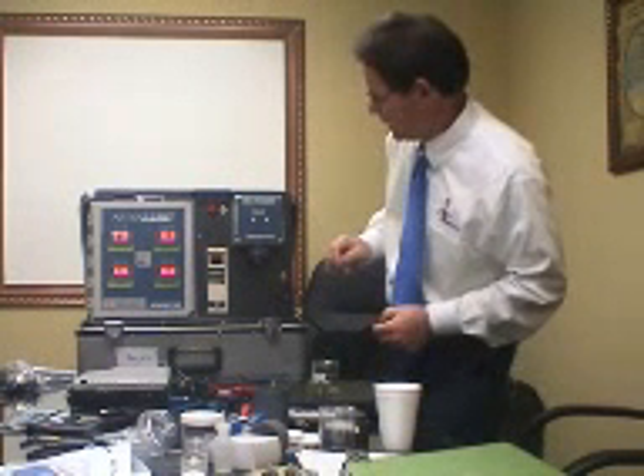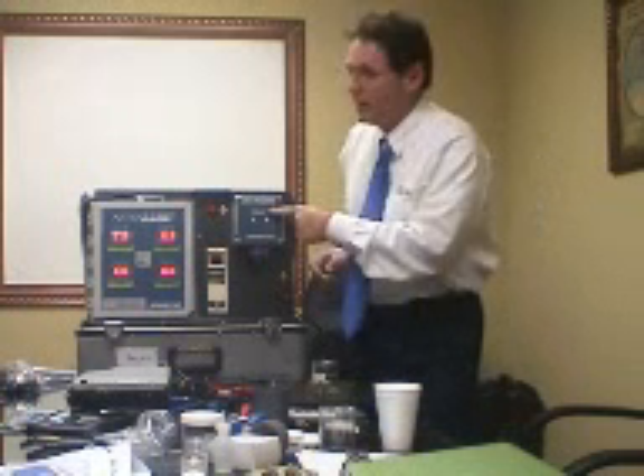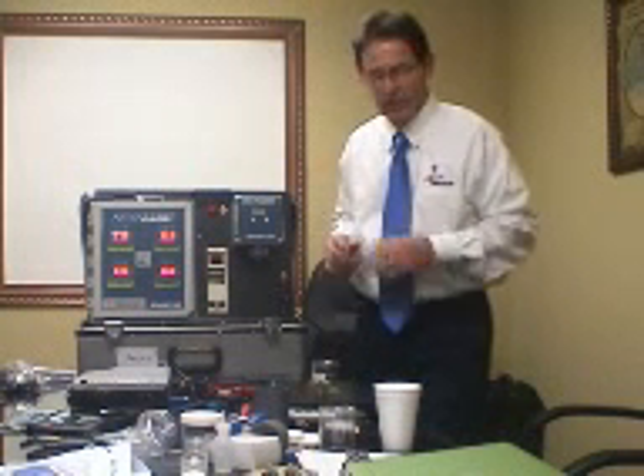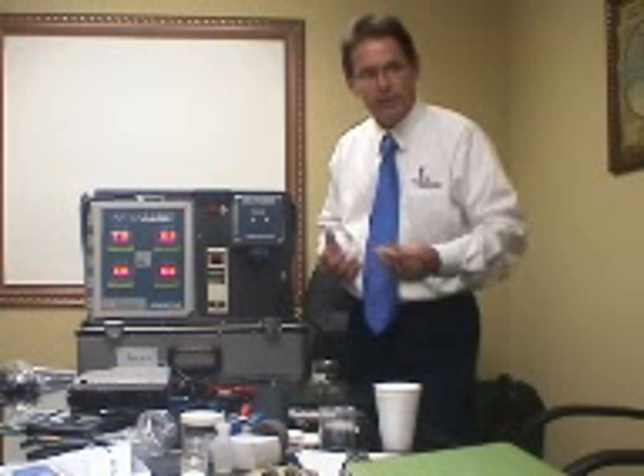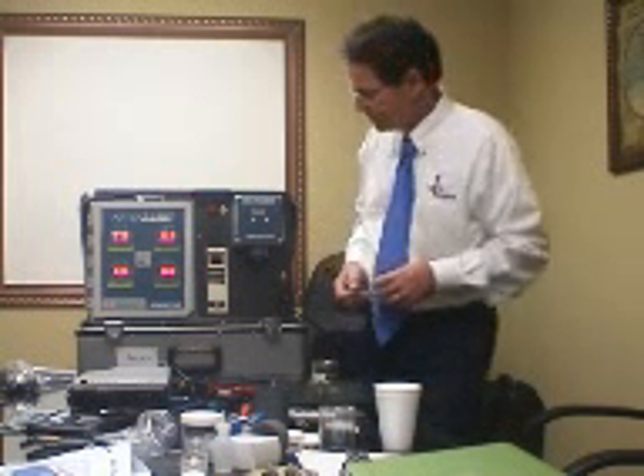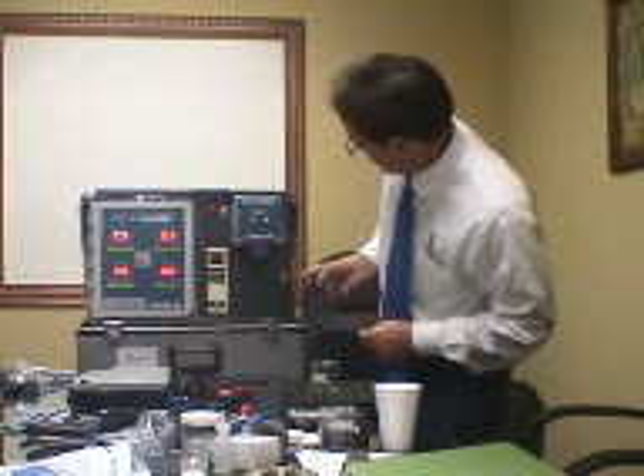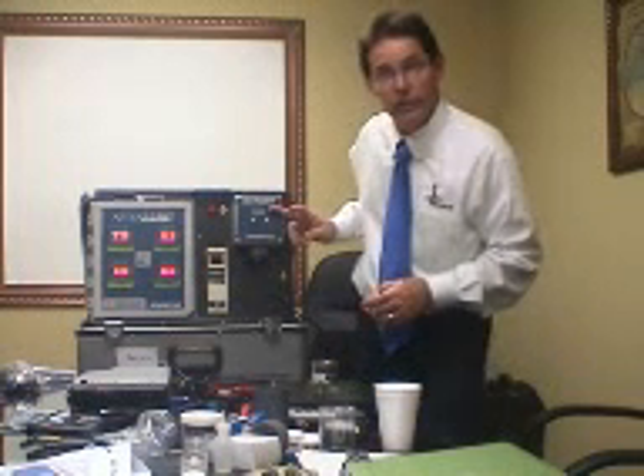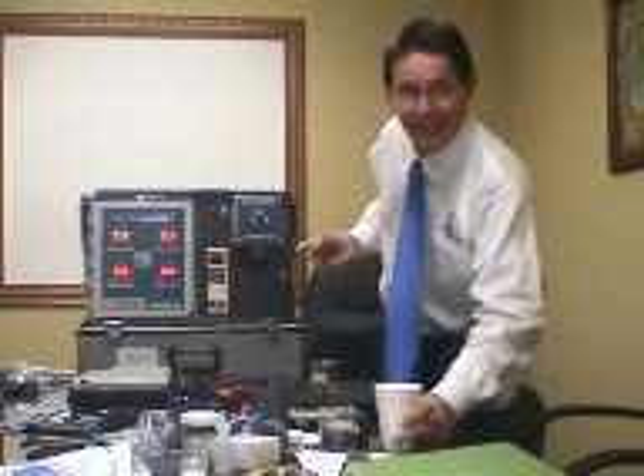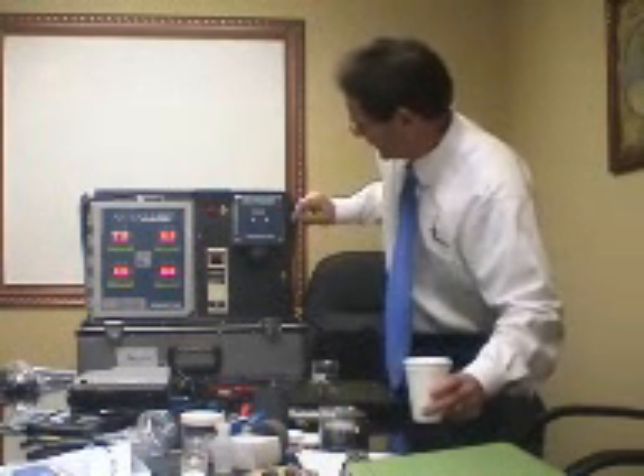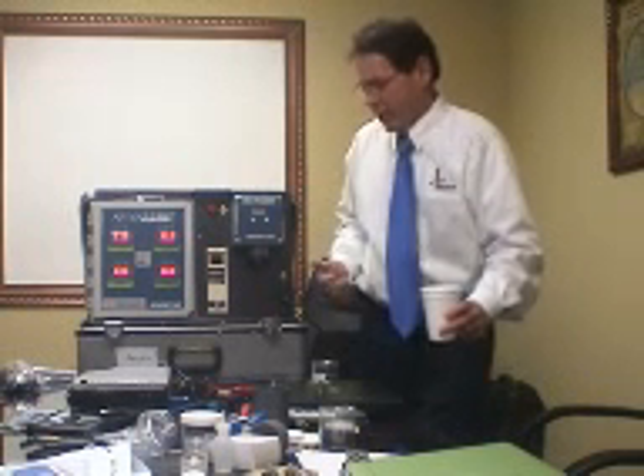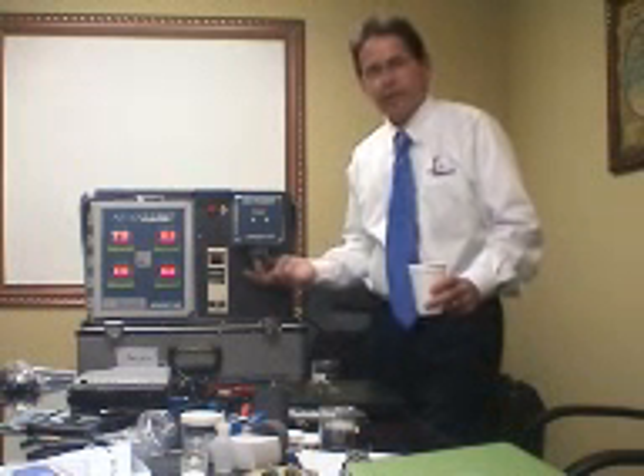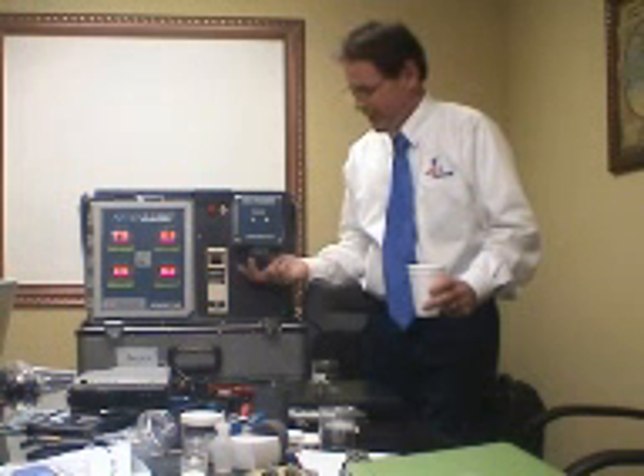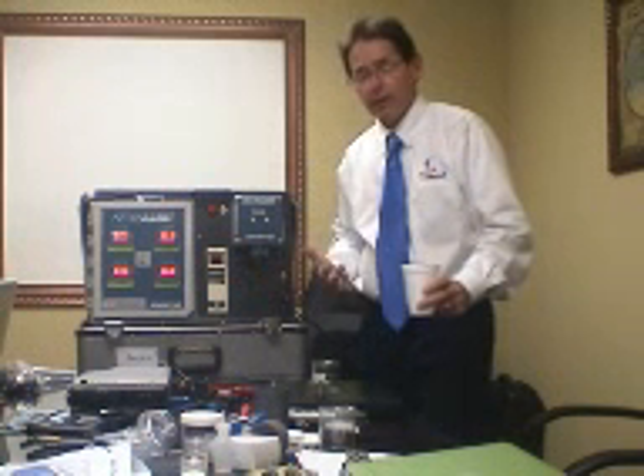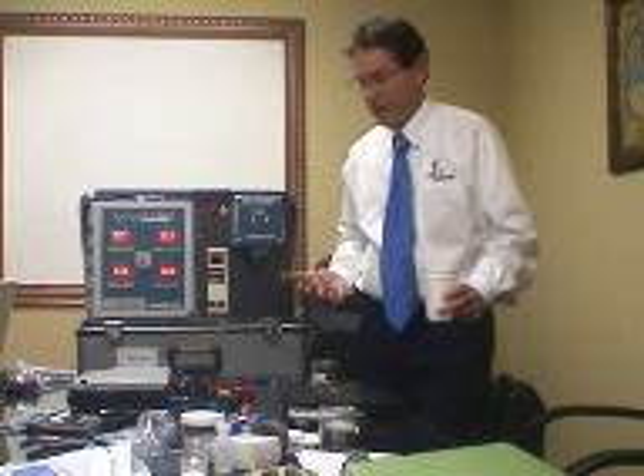So it's giving me 10 seconds before it tells me, right there, apply gas now. It's going to assume that I'm finished changing it, and it's going to say, okay, put the gas on. It says cal mode, and now it's calibrating. And instead of applying a cylinder of gas on this, we're using the ambient air and assuming it's 20.9.